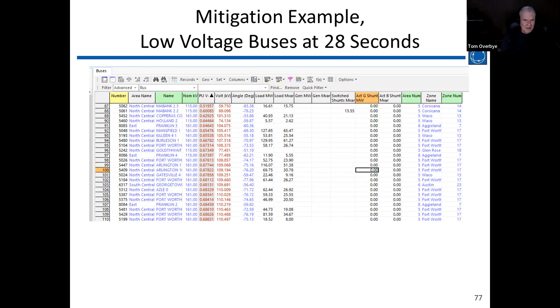This is a mitigation example where I went into this 52 volt per kilometer scenario. I ran the simulation, then used the save power flow snapshot to go back to 28 seconds and started playing around with the system. For example, I looked at the bus voltages and saw a voltage at a load bus that's 0.5 per unit. The customers at that bus are not too happy, so maybe we should get rid of that bus, or at least its load. I got rid of the load, and that caused the voltages to recover.